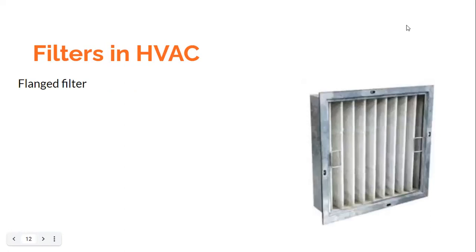The next type comes with a flange around it, and the flange is on either the entry side or the exit side, and sometimes on both sides. What does the flange do? It allows the filter to be rigidly mounted on the mounting frame. We can use a clamp or a bolt-and-nut arrangement. Because of the flange, one can use a bolt-and-nut arrangement or a clamp, giving a good leak-free fit. This is a flange filter — by looking at the diagram you should be able to identify it.